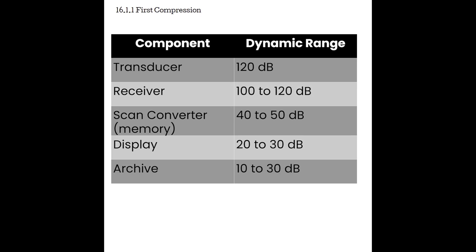By the time we are printing pictures on that little thermal printer connected to the machine, we're taking signals that can reach up to a trillion in differences down to tens, hundreds, or thousands of differences. This is why dynamic range has to be reduced and why compression occurs. As those signals are processed, we don't want to lose information about the strongest or weakest signal, so we need to compress them together — make their differences less drastic without losing the hierarchy of strength. Through compression, we make sure each system component does not introduce any errors into the image.